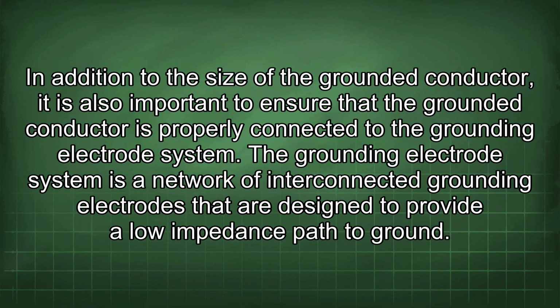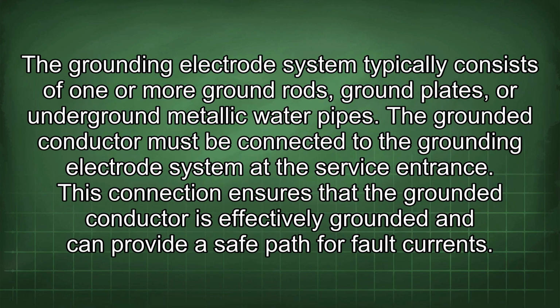In addition to the size of the grounded conductor, it is also important to ensure that the grounded conductor is properly connected to the grounding electrode system. The grounding electrode system is a network of interconnected grounding electrodes that are designed to provide a low impedance path to ground. The grounding electrode system typically consists of one or more ground rods, ground plates, or underground metallic water pipes. The grounded conductor must be connected to the grounding electrode system at the service entrance. This connection ensures that the grounded conductor is effectively grounded and can provide a safe path for fault currents.